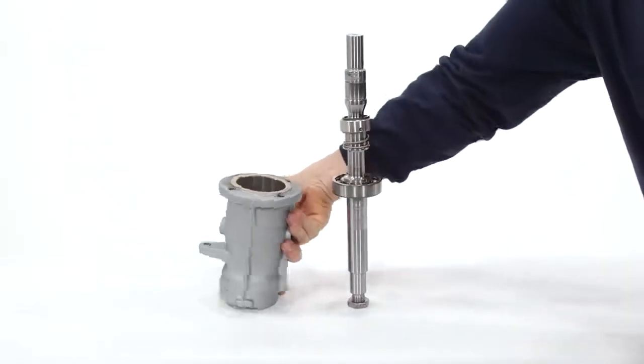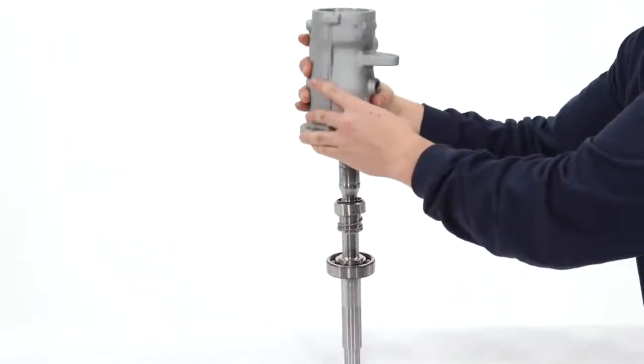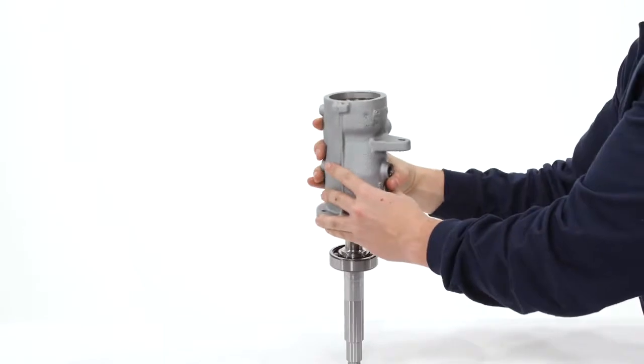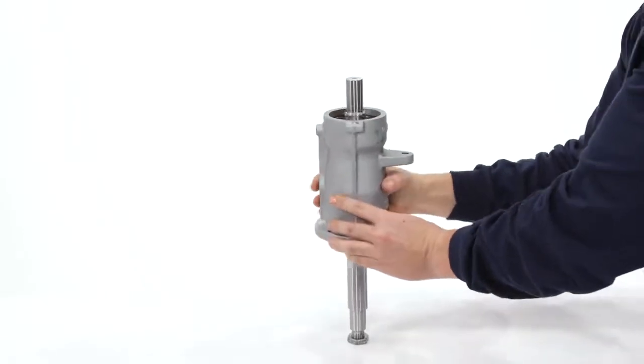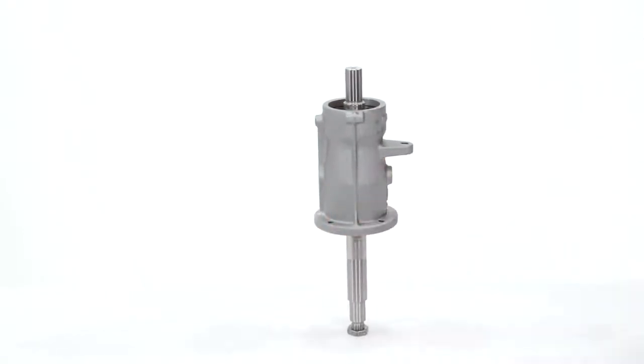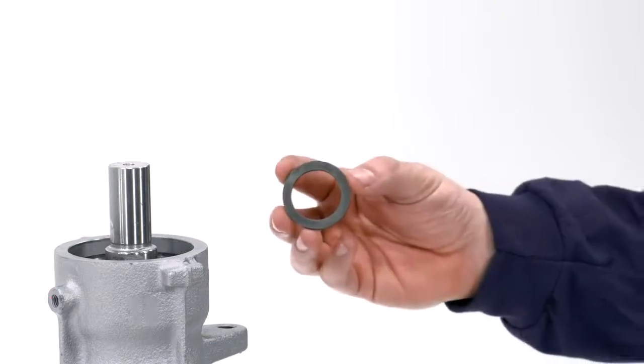Insert the shaft assembly into the bottom of the pump bearing frame. Be careful not to damage the mechanical seal. Add the spacer around the shaft and onto the grease cover.